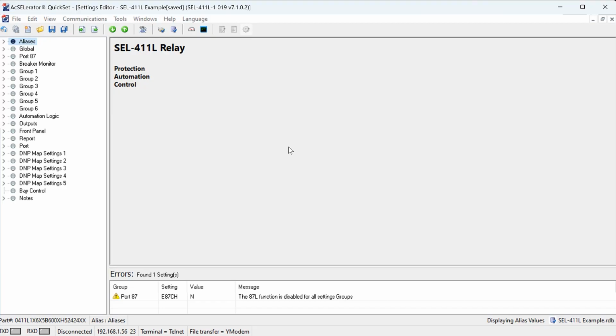All right, so what I have over here are just default settings for an SEL-411L relay. And in here, of course, I'm going to be focusing on the sync check element. But of course, if you were to implement these settings for a real-life application, you would need to program all the other settings. Just know that for this example, we're just going to focus on the sync check settings.